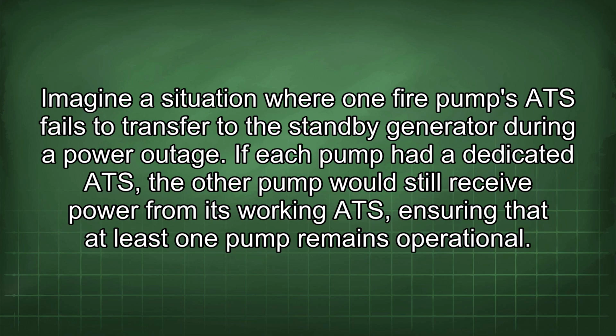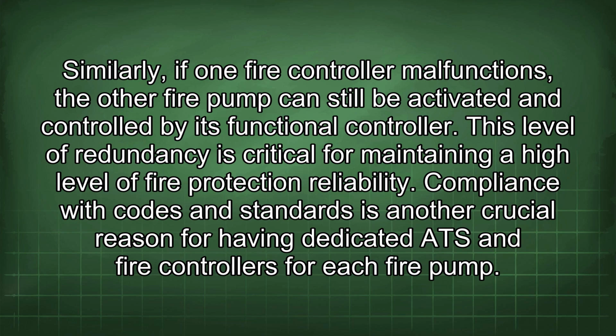Imagine a situation where one fire pump's ATS fails to transfer to the standby generator during a power outage. If each pump had a dedicated ATS, the other pump would still receive power through its working ATS, ensuring that at least one pump remains operational. Similarly, if one fire controller malfunctions, the other fire pump can still be activated and controlled by its functional controller. This level of redundancy is critical for maintaining a high level of fire protection reliability.